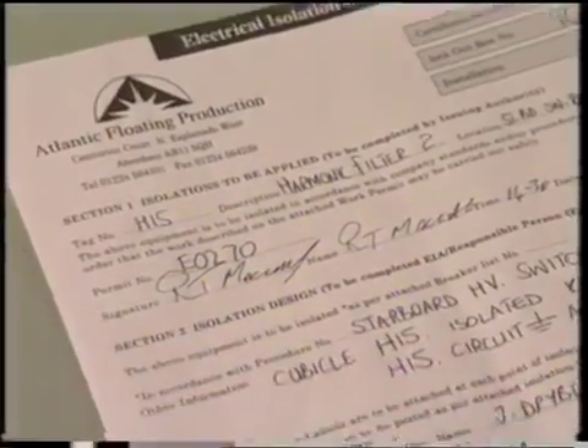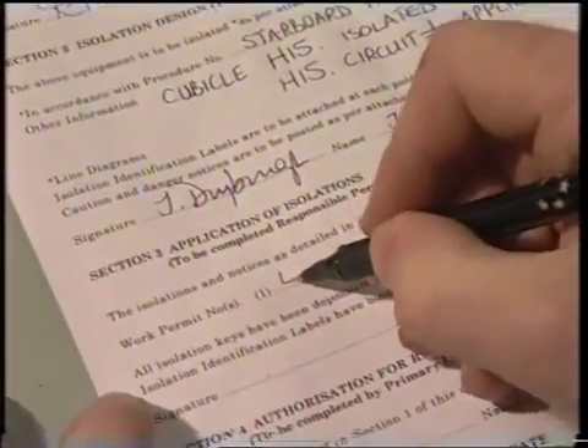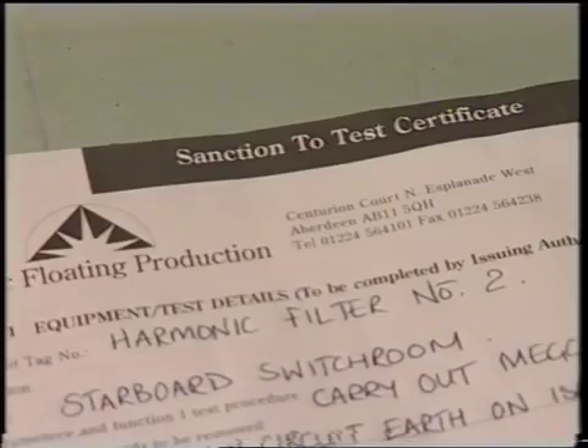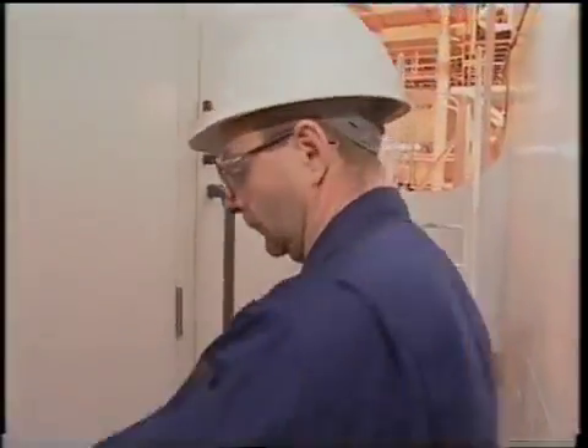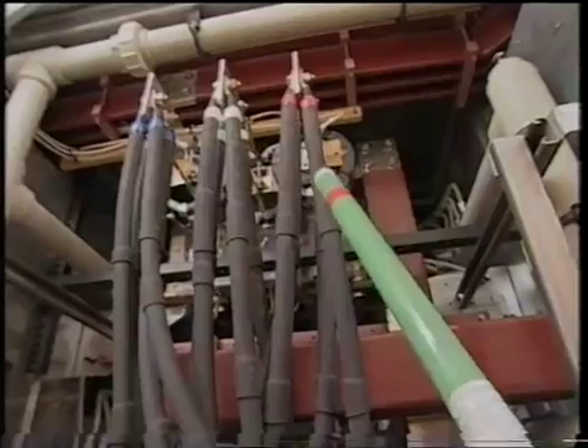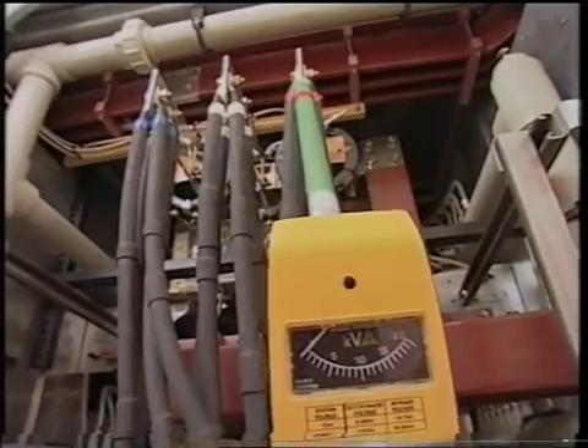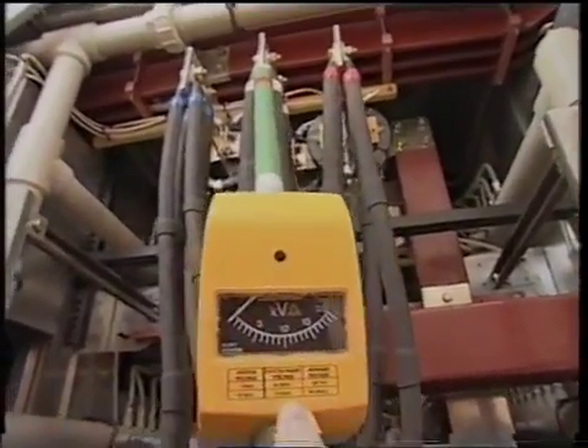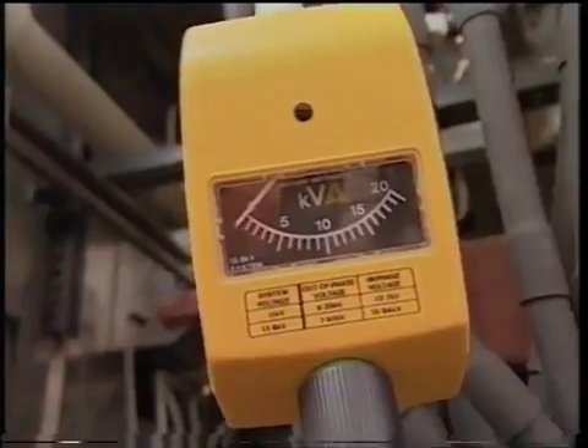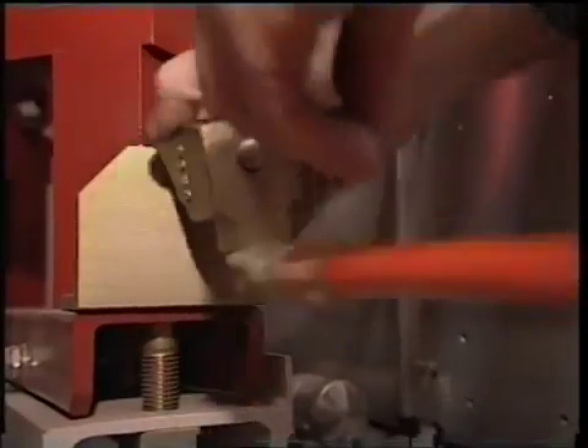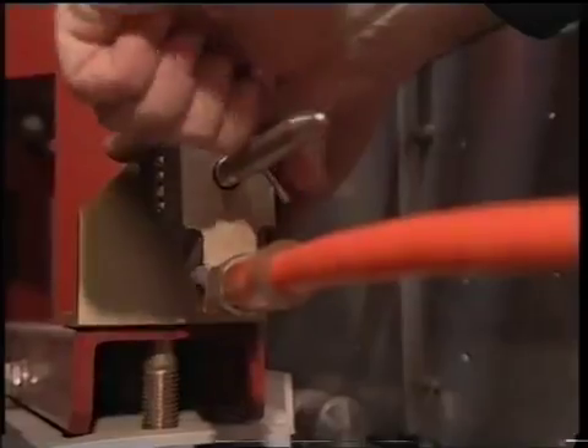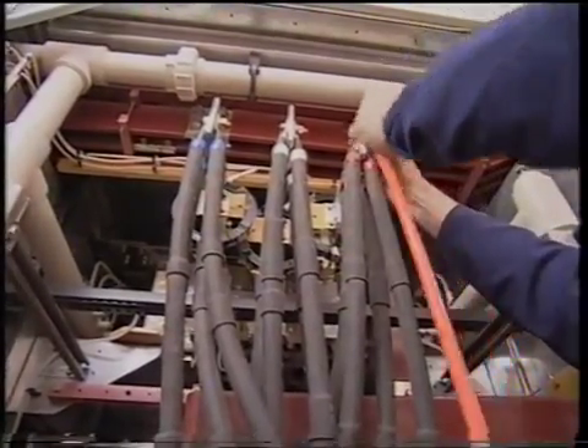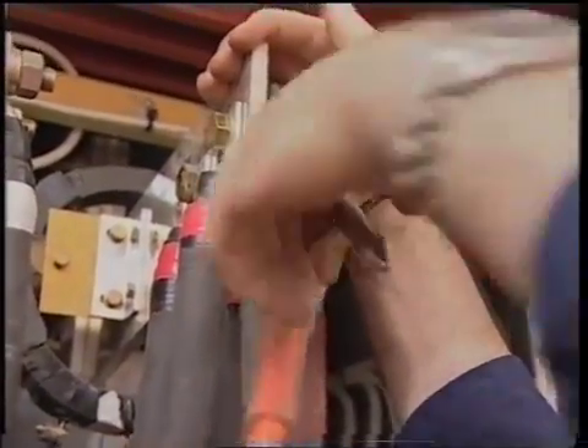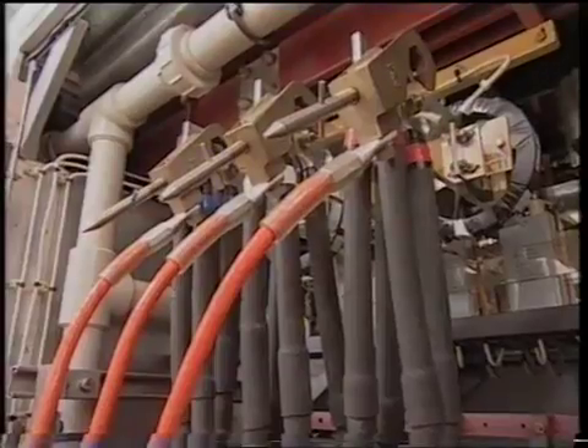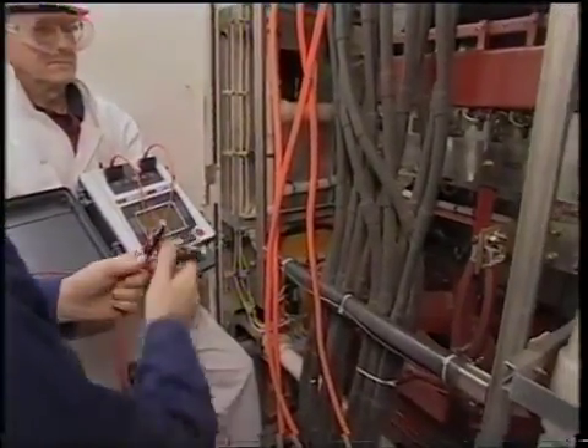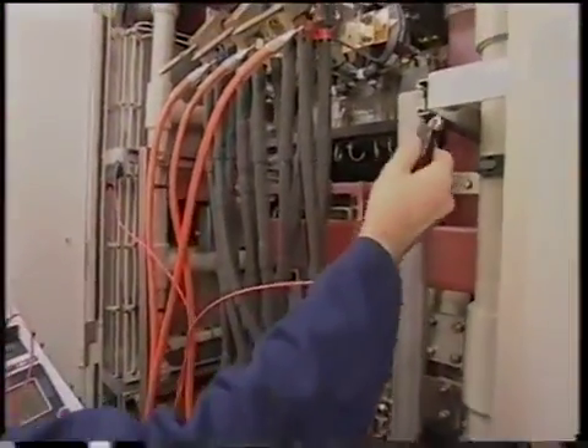At this point, the isolation certificate can be completed and the sanction to test filled out. Now the CETO proceeds to the high voltage equipment he needs to test. Again, the HV prod is used to confirm the circuit is dead. Portable earth leads are connected to each phase to form a local additional earth connection for operator safety. The 5 kV insulation resistance tester is now connected, while the additional earth is still connected.